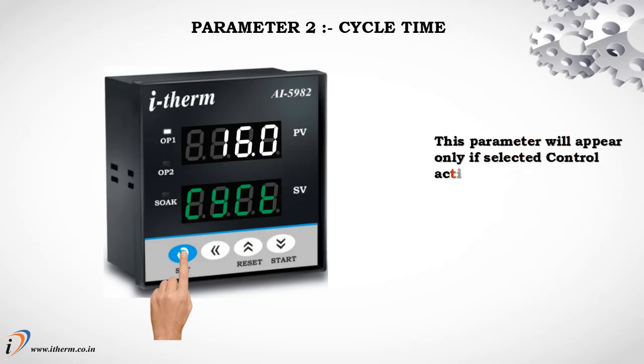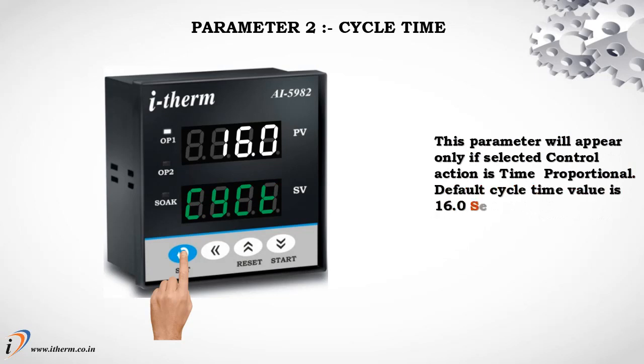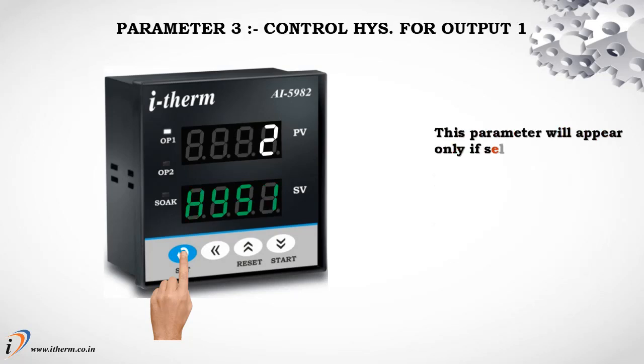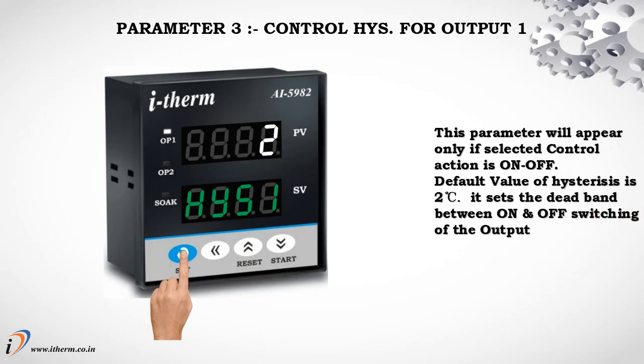Parameter 1: Proportional Band. This parameter will appear only if the selected control action is time proportional. Default value for proportional band is 5.0. Parameter 2: Cycle Time. This parameter will appear only if the selected control action is time proportional. Default cycle time value is 16.0 seconds for relay output and 1.0 seconds for SSR output. Parameter 3: Control Hysteresis for Output 1. This parameter will appear only if the selected control action is on/off. Default value of hysteresis is 2 degrees centigrade.